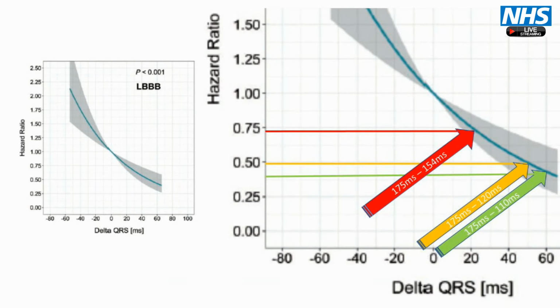So what have we demonstrated today? We've demonstrated how we can add incremental benefit to our CRT patients through an easily achievable personalisation protocol with clear, measurable targets. In general, this takes less than 10 minutes and is achievable before the pocket is closed. In Mr. Ayoub's case, if we consider the programming choices made and apply this to the clinical papers we've reviewed, we can visualise the potential reduction in the hazard ratio with each step. On this final slide, the red arrow is QRS duration and hazard ratio out of the box settings. Yellow is with good single point CRT, and green is with the addition of multi-point pacing.